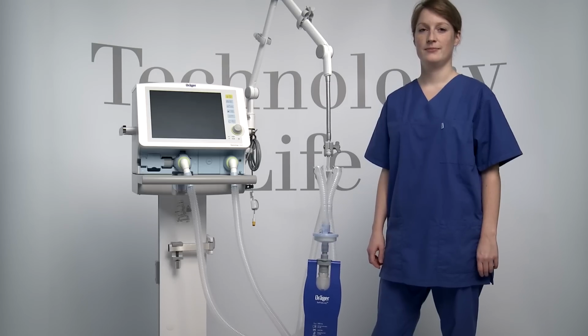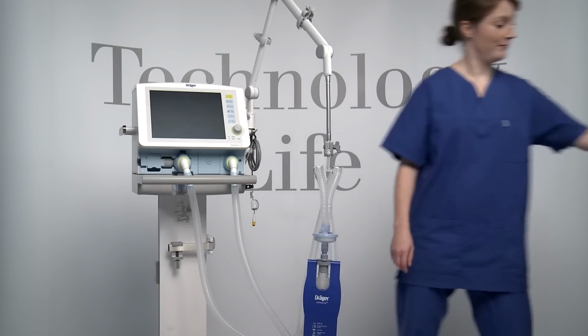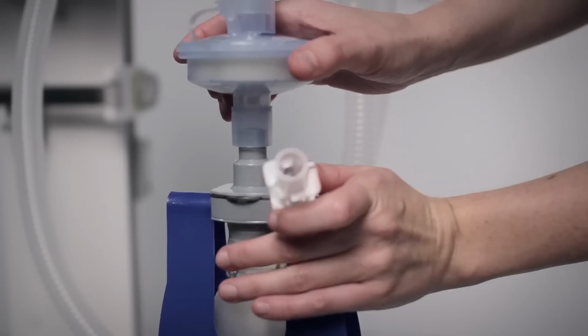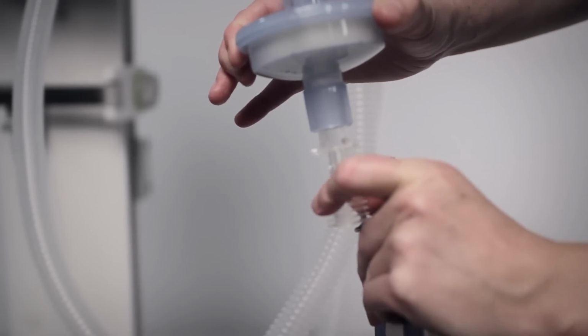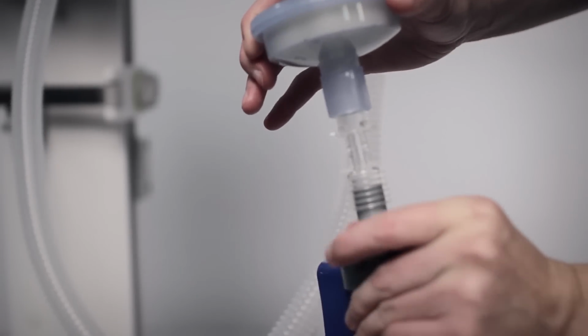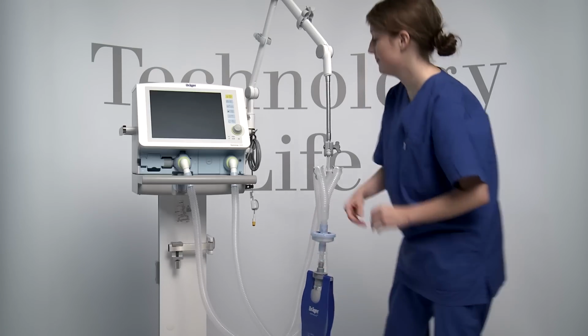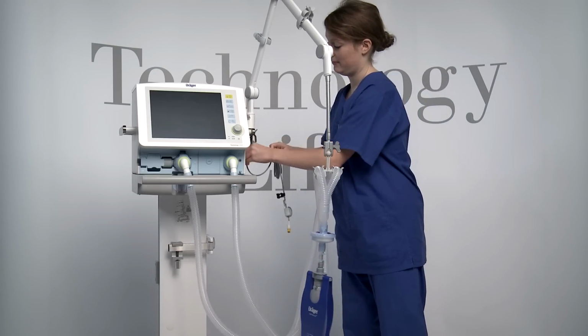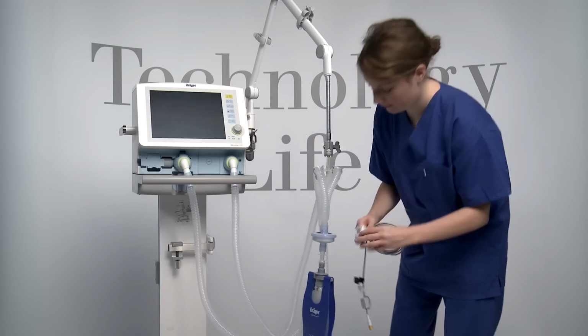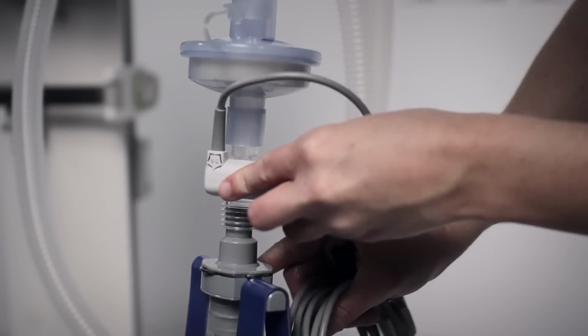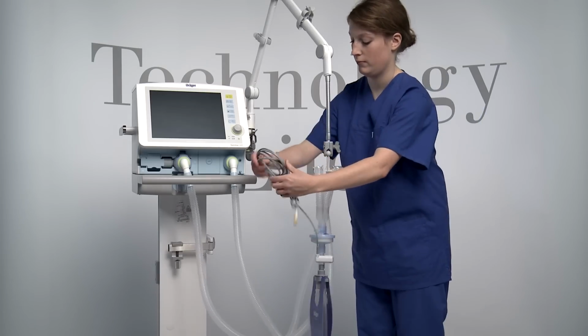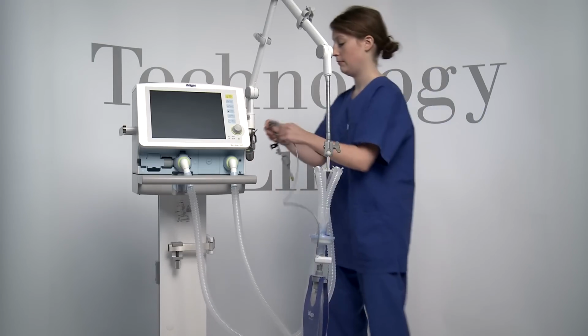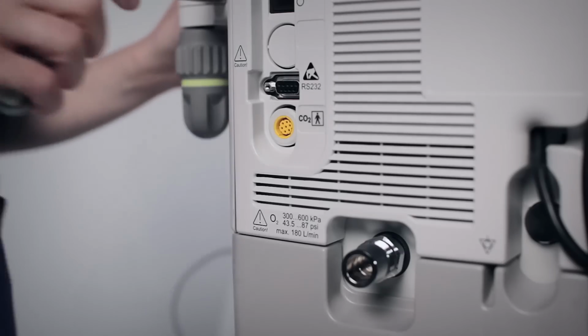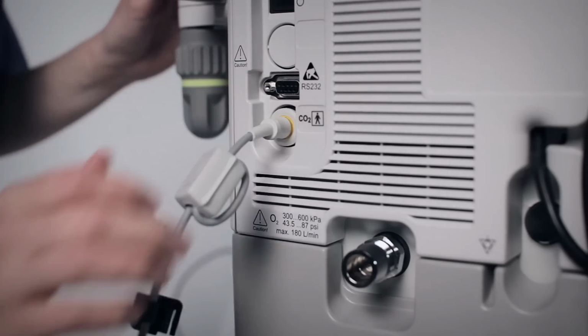The option CO2 offers the possibility of a CO2 mainstream measurement directly at the Y-piece and delivers measuring data in real time. They are shown as a graphic and as numerical values on the screen of the ventilator. Insert the cuvette into the patient connector of the Y-piece so that the cuvette windows are facing to the side. Afterwards, push the CO2 sensor onto the cuvette. The cable is facing towards the device. Insert the connector of the CO2 sensor into the socket on the rear of Savina 300.